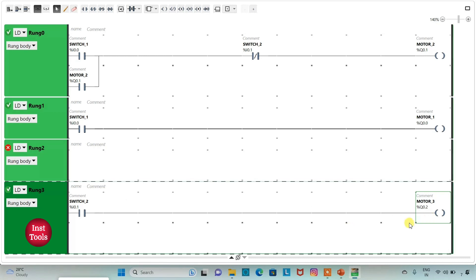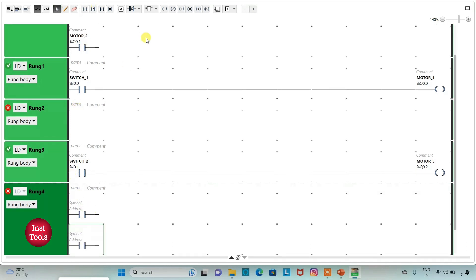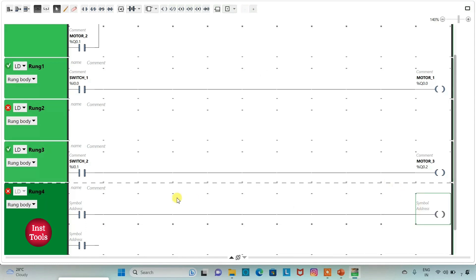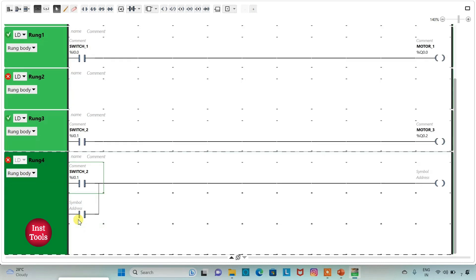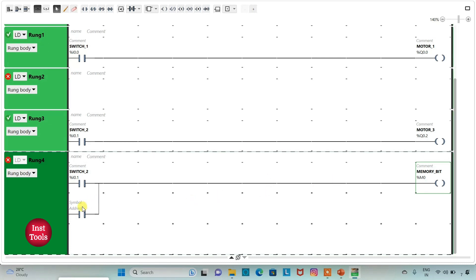And when switch 2 is off, motor 3 will be off. I will add a new rung and insert two normally open contacts and one coil, connecting the normally open contact by drawing a line. I will assign address I0.1 to one contact, and address M0 with symbol 'memory bit' to the coil. I will latch this memory bit by assigning the same address M0 to the parallel contact. So when switch 2 is on, the memory bit will be true, and when switch 2 is off, the memory bit still remains true.